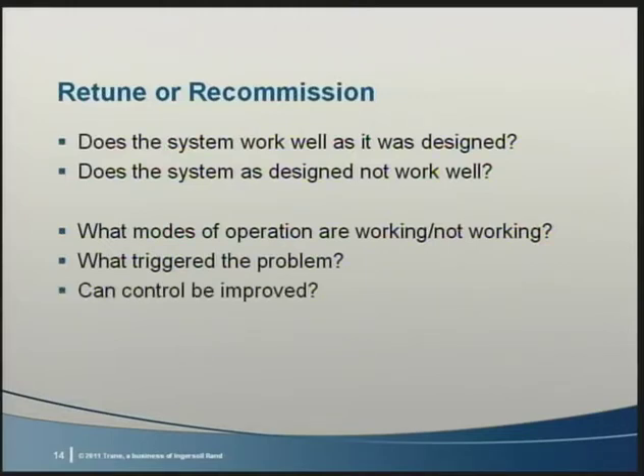Prudent use of controls can help. Features like optimal start can identify the right amount of time needed to change modes. Is the controller acting too slowly or hunting? Now, you can't fix a chilled water system until you know what the problem is. It may be that the chilled water system performance is not the cause, but the symptom of a badly operating building. The data is out there, usually too much data. By seeking out data, converting it to information, and then acting on it, you can identify and correct building energy waste. Let's look at two examples of data turned into actionable information about how a building is operating.